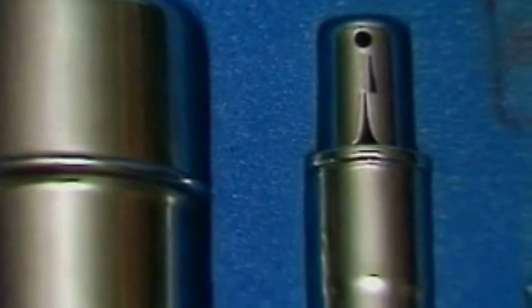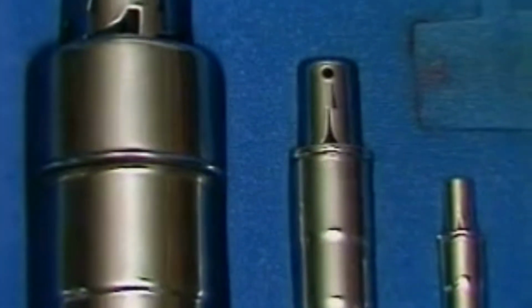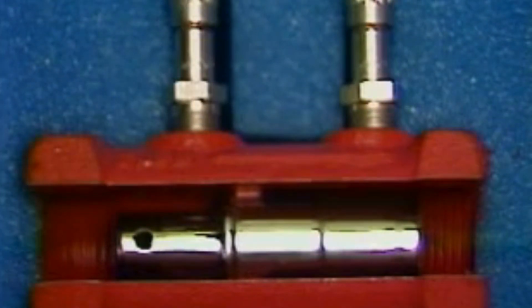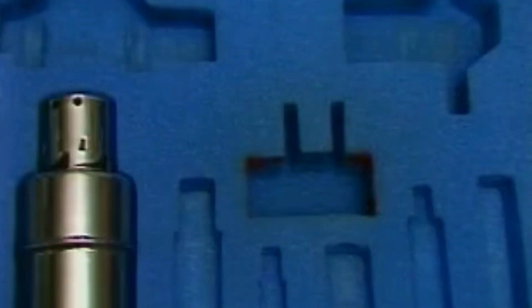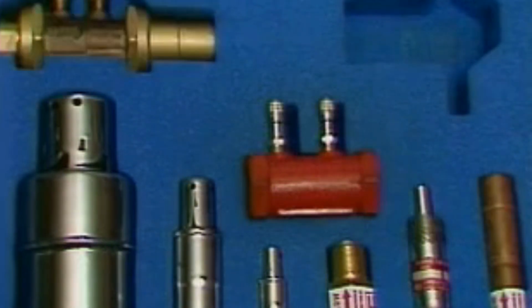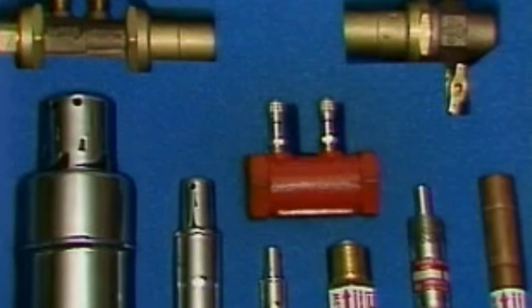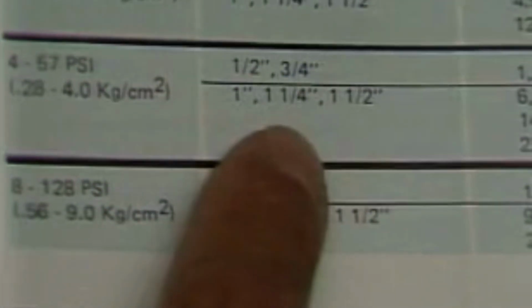The system is designed so that there are no adjustments. The flow control cartridge is calibrated at the factory, so you have to order the correct cartridge for the job it's going to do. The cartridge fits into a body, and the body comes in several styles. How do you select the valve for your application? Simple. Choose the material of valve construction you need, stainless or Monel, and the differential pressure range. Then use the Griswold valve selection chart to pick the factory-set GPM flow rate that meets your requirement. The flow rate will determine the valve size. If the size is different from your system, standard adapters can be used to make the connection. Here's the one we use most often on our rigs.